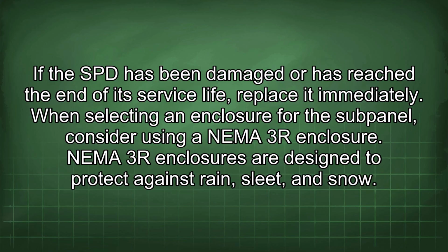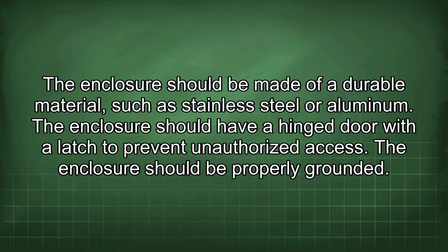When selecting an enclosure for the subpanel, consider using a NEMA-3R enclosure. NEMA-3R enclosures are designed to protect against rain, sleet, and snow. The enclosure should be made of a durable material such as stainless steel or aluminum. The enclosure should have a hinged door with a latch to prevent unauthorized access. The enclosure should be properly grounded.